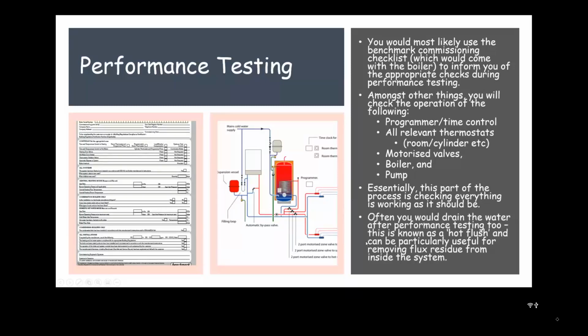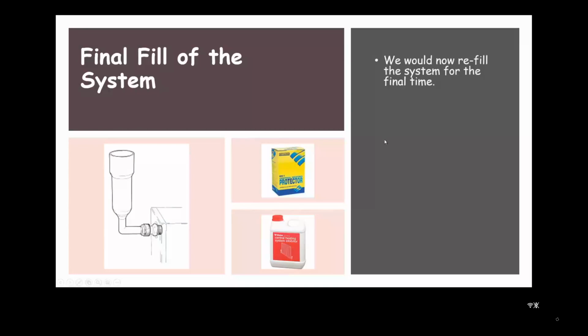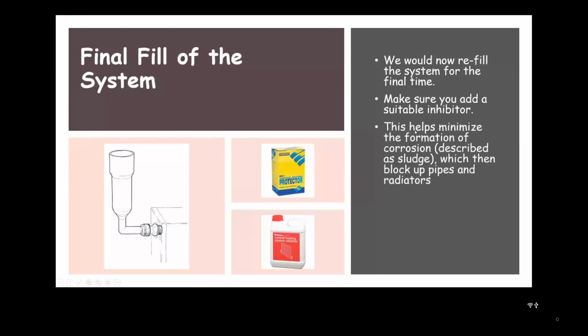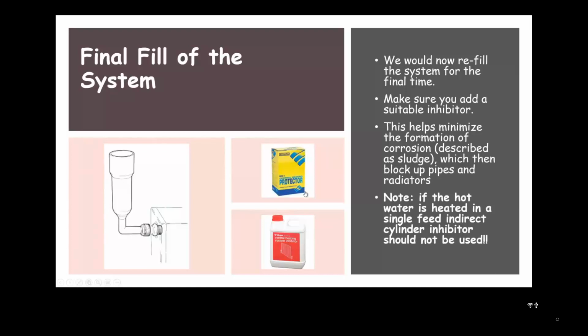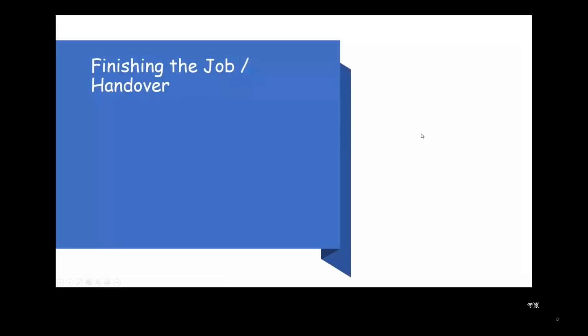After you've done the performance test, you will have put some heat into the system and round the system. It's often a good idea at this point to let that water go again, release it from the system, and that would be described as a hot flush. It can be particularly useful for removing extra flux residue from inside the system. So now we do a final fill. We fill the system for the last time. Make sure you use a suitable inhibitor. Inhibitor is there to prevent corrosion, minimise the formation of corrosion, which can block up our pipes and radiators. Though if you are commissioning a system which is connected to a single feed indirect cylinder, you must not use inhibitor, because there's a potential for that to vent into the hot water side, which is obviously something we would like to avoid.